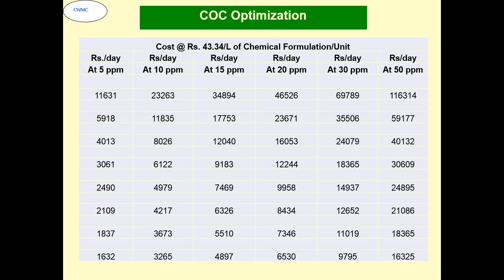This is the cost, continuation of the same thing. You see the cost is reducing drastically, even at say 30 ppm, it is about say 10,000 rupees per day compared to about 5 ppm at about say once through system or 1.5 COC. So there we are putting about 11,631, and here less than 10,000 even at 30 ppm dosage. So that is what I meant when I say that your overall cost goes down.